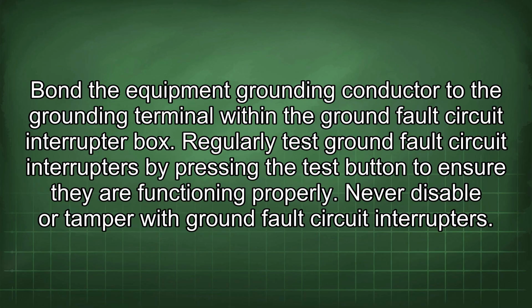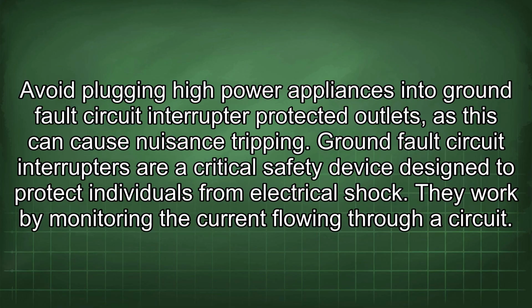Bond the equipment grounding conductor to the grounding terminal within the ground fault circuit interrupter box. Regularly test ground fault circuit interrupters by pressing the test button to ensure they are functioning properly. Never disable or tamper with ground fault circuit interrupters. Avoid plugging high-power appliances into ground fault circuit interrupter protected outlets, as this can cause nuisance tripping.